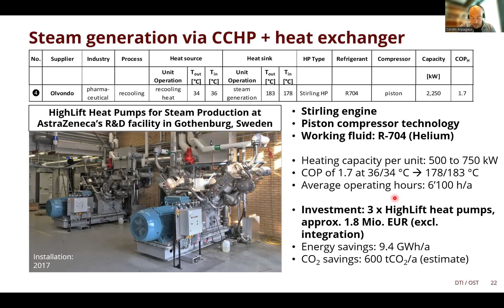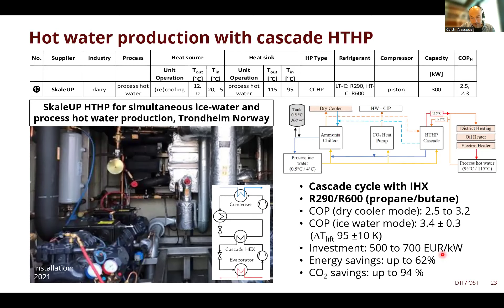Then this demonstration case is about a SkaleUP cascade high temperature heat pump, which is here for simultaneous process heating and cooling. It has been developed by Sintef in Trondheim in Norway, and it has been demonstrated at the dairy of Tine in Norway. So it's a cascade heat pump using propane in the lower stage and butane in the upper stage as refrigerants. The heat pump can run in an ice water production mode or in a dry cooler mode. So in the ice water production mode, a COP of 3.4 is reached. And here the COP is the combined COP of heating and cooling. So the specific investment cost for this 300 kilowatt heat pump unit is between 500 to 700 euros per kilowatt.